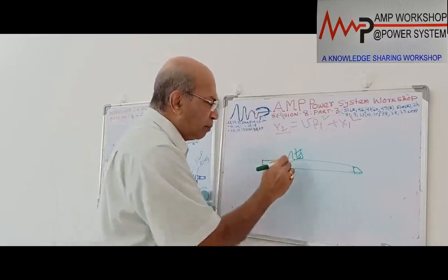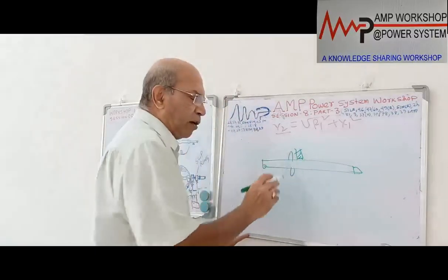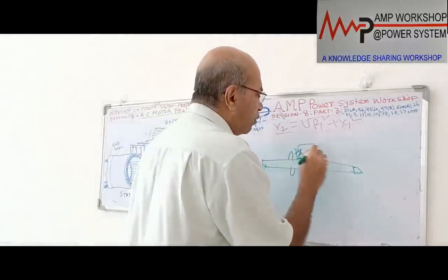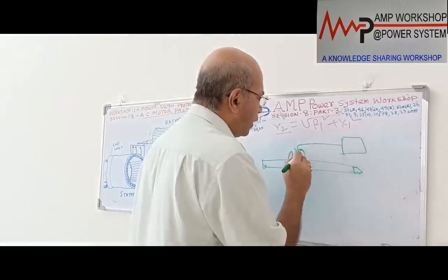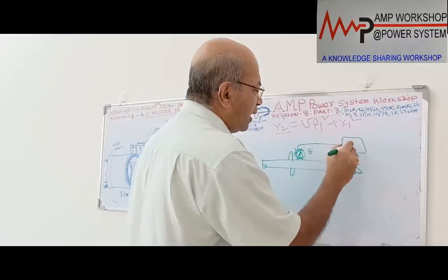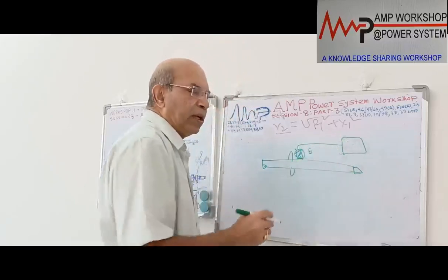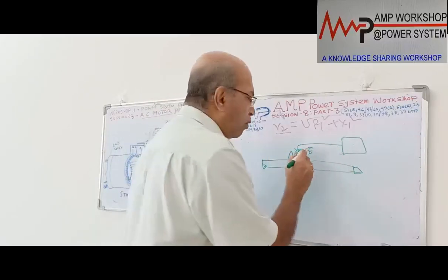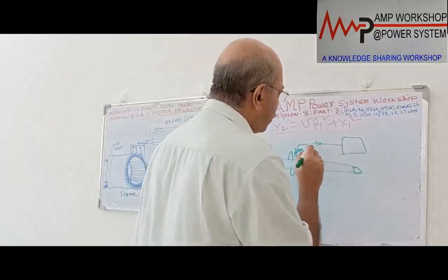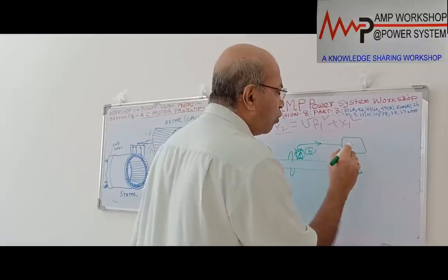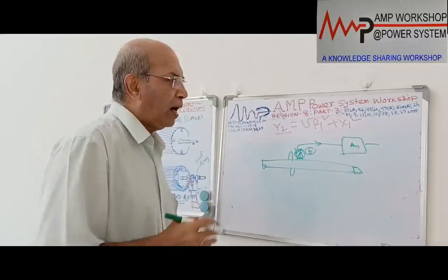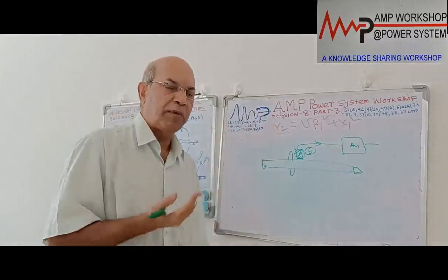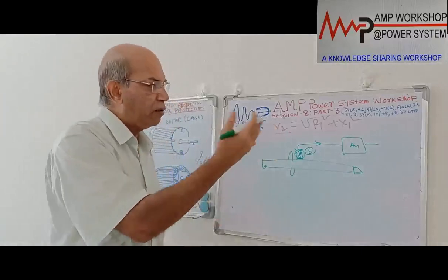Those sensors will pick up the signal, and the signal will go to the device where it will be converted. All output is electrical in nature. If it is a resistance output, then it will go to a Wheatstone bridge. If suppose it is a current output of the pickup, then the current will go to the amplifier, and then it will drive the respective equipment, a relay, and that will give an alarm or trip command for the motor when the vibration goes above this.